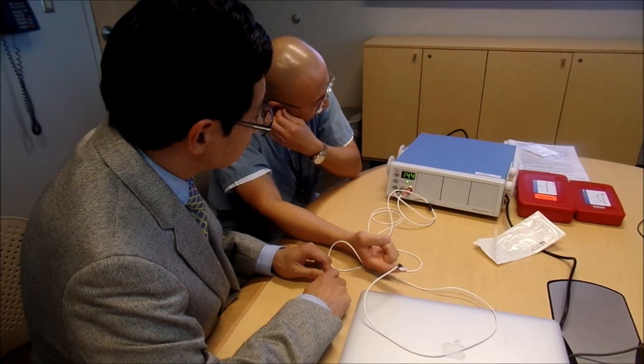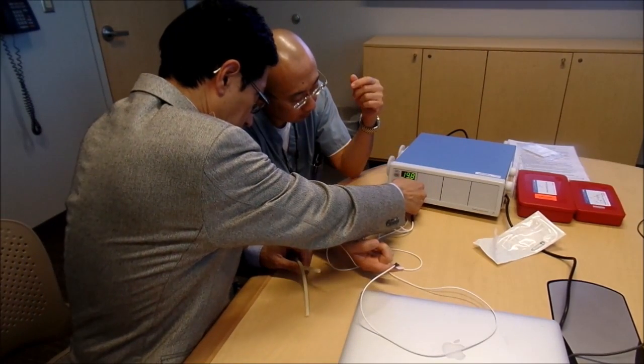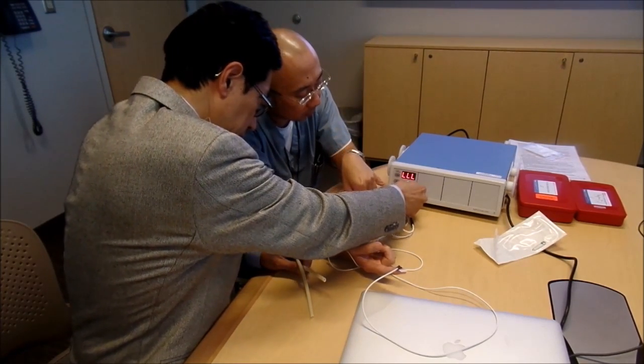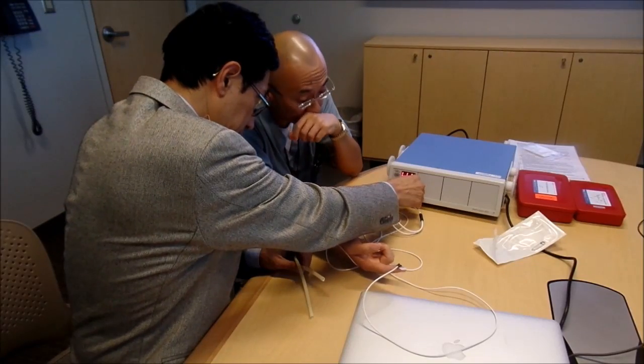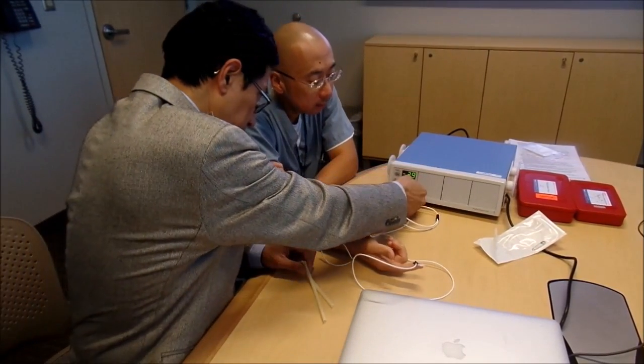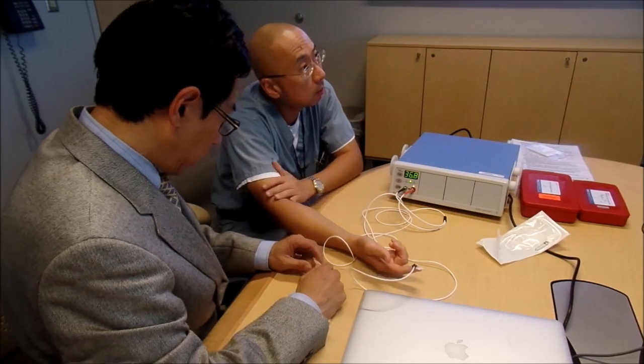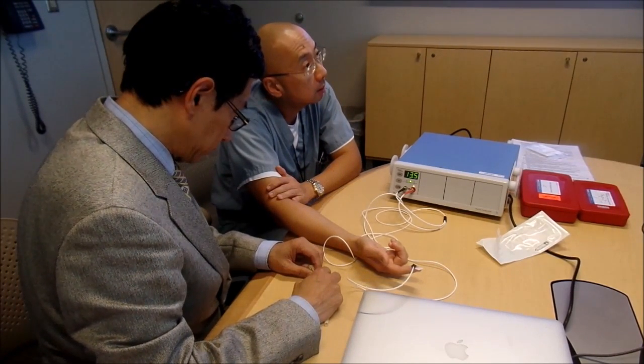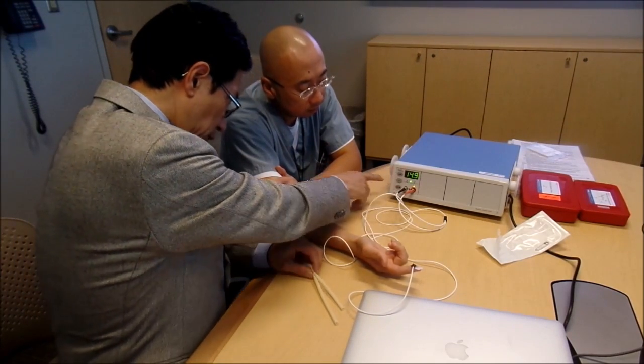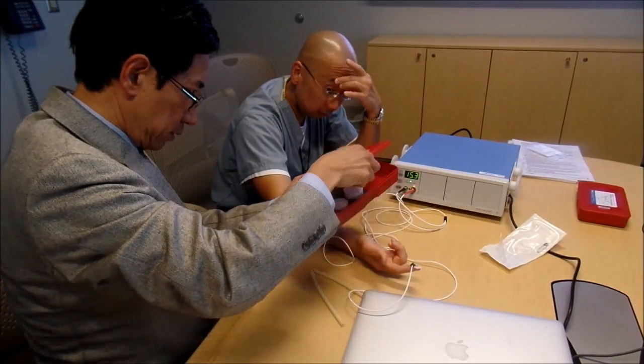So how do you turn this on? So these are the cables? Right, the cable. It's not disposable. So you pull it out and you have to push in. Red with red, black with black. So they come with two of them, is that correct? Yeah, transmitting and receiving. It's like a Luer lock, you push in and turn. And that's all you need to do, you don't have to calibrate it? Calibrate if you replace the probe, and I'll go over those details. Basically when you're working with the monitor, you don't want to push the calibrator, because you have to have the proper solution to calibrate it.